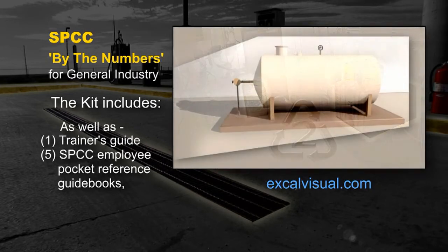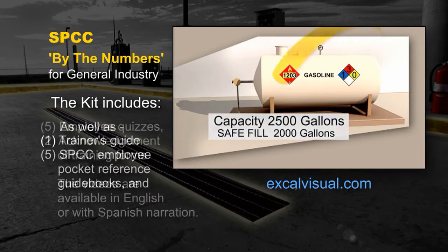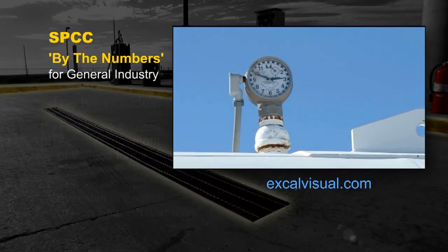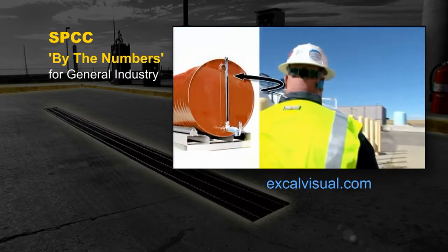Containers should be labeled with the type of oil. Labeling will often include the capacity, the safe fill level, and an ID number when applicable. Bulk tanks and fuel pumps are usually equipped with some type of overfill protection. This may be an automatic device installed in the fill system, or it may be a high-level visual and/or audible alarm.